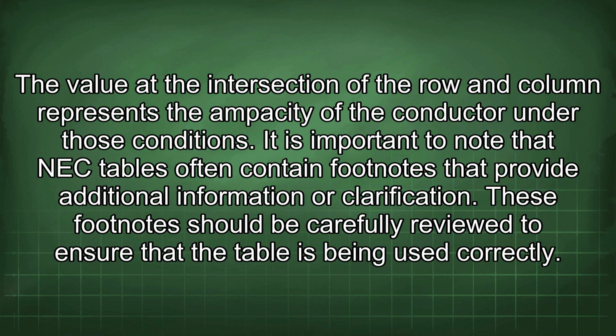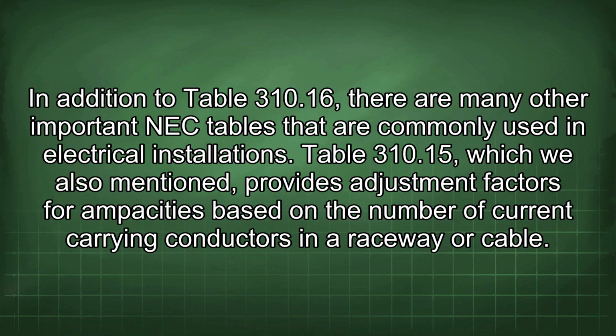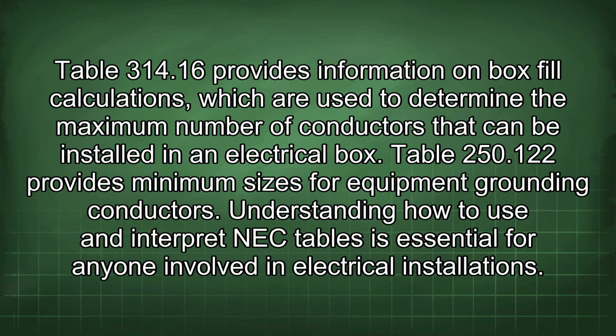It is important to note that NEC tables often contain footnotes that provide additional information or clarification. These footnotes should be carefully reviewed to ensure that the table is being used correctly. In addition to Table 310.16, there are many other important NEC tables that are commonly used in electrical installations. Table 310.15, which we also mentioned, provides adjustment factors for ampacities based on the number of current carrying conductors in a raceway or cable. Table 314.16 provides information on box fill calculations, which are used to determine the maximum number of conductors that can be installed in an electrical box.